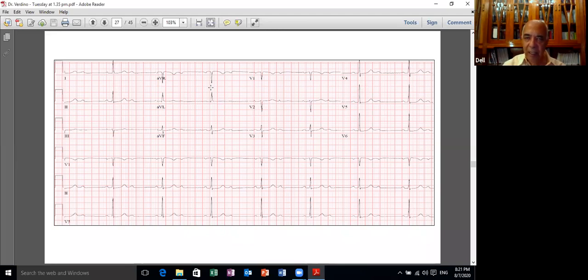So the pacing mode here should be an AAI. The AAI here is not pacing the atrium because the atrial rate is more than the lower rate limit, and is not knowing what's happening in the ventricle because there is no ventricular lead to inform the pacemaker about the ventricular events. So it's an AAI. So as you see here, you are not doing anything for the patient. The patient is unprotected, and this is the reason we are not putting too many AAI, although it has a lot of advantages, as I will point out.